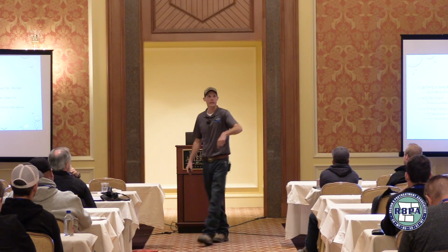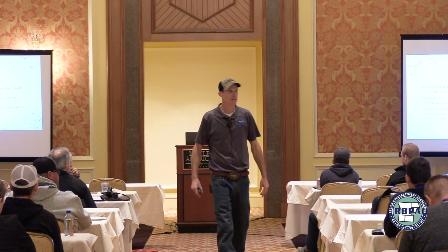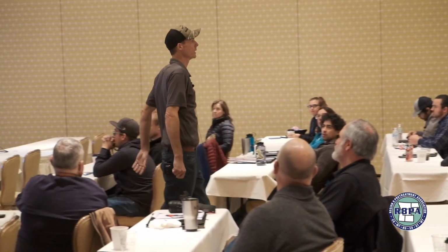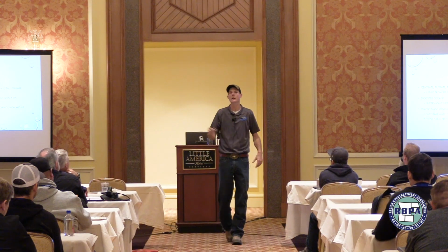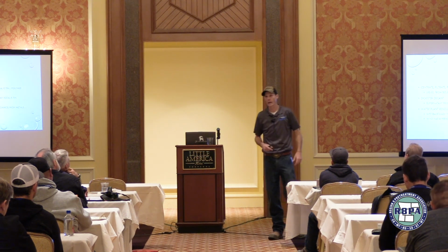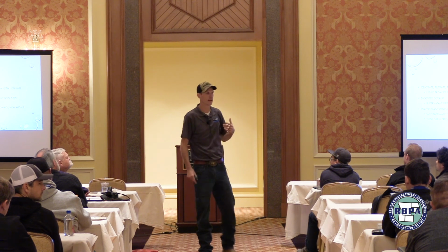I had a question. Who has a water plant in their service area and permits them with an industrial pretreatment program? Sort of? I wish everybody in the room would raise their hand, because this is going to be a big deal pretty quick. Jessica works for me. Jessica was over at a city here not that long ago. They plugged up their pipeline going to the wastewater plant from water plant backwash. And how thick was that scale in the manhole? Three to four inches of just goo that they scraped off the walls of a manhole. And nobody could tell us how long it had been there.